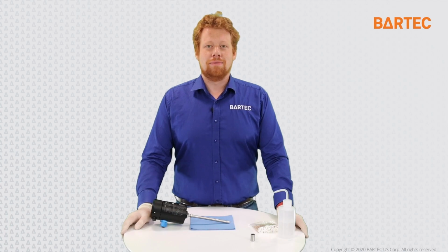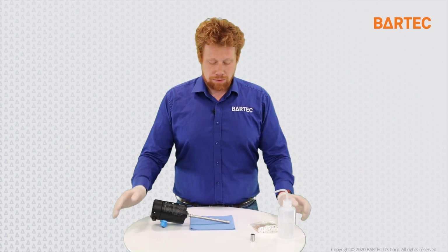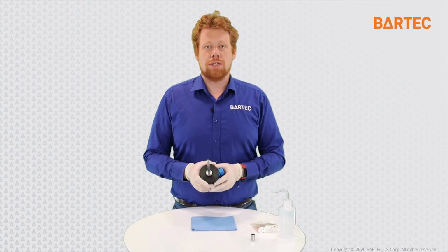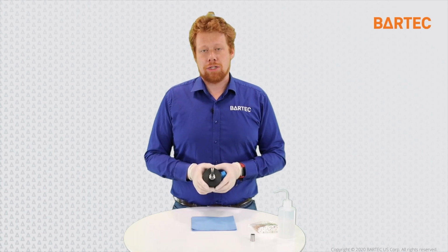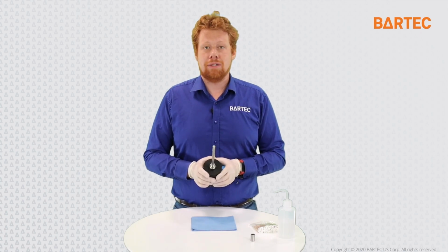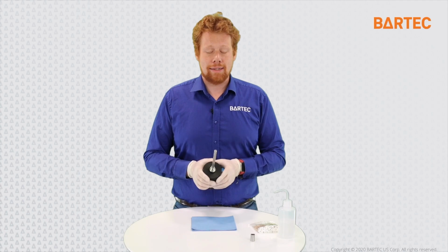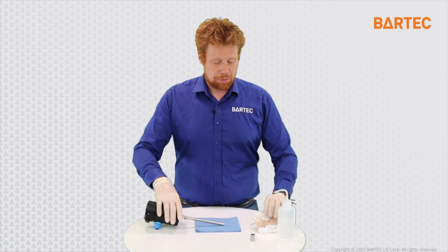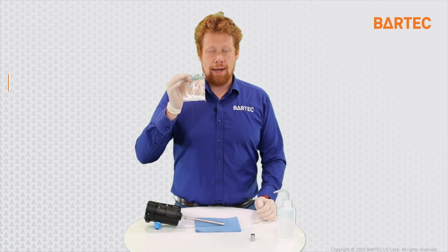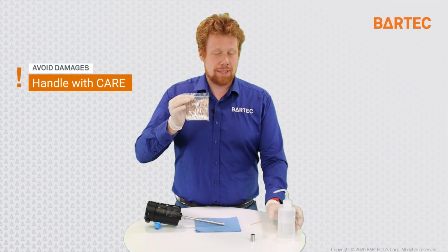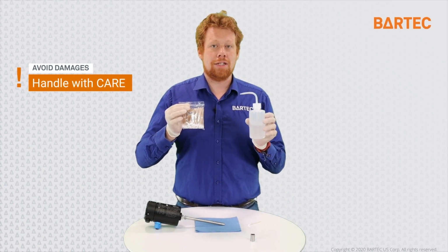The last thing I want to cover with you is the maintenance aspect of the Hygrophil probe. The maintenance requirements of the Hygrophil probe are low. We recommend that at least once a year or more, depending on process requirement, the probe be taken out of the process and cleaned. To clean it, we will require two things: analyzer grade Q-tips and IPA, isopropyl alcohol.